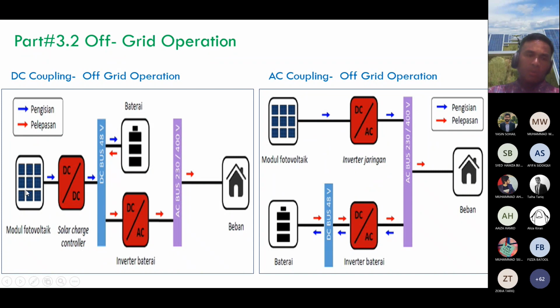For this system, when we use a battery, we couple it to the DC bus. That means from the PV module, there is a solar charge controller, and we also have a battery, and together they mix in the DC bus. Then from the inverter, the battery power will convert from DC to AC, then deliver to the AC bus and to the load. So the battery is only two-way: the PV will charge the battery, and the battery will deliver DC power to the DC bus, then the inverter will convert it to AC power later on.